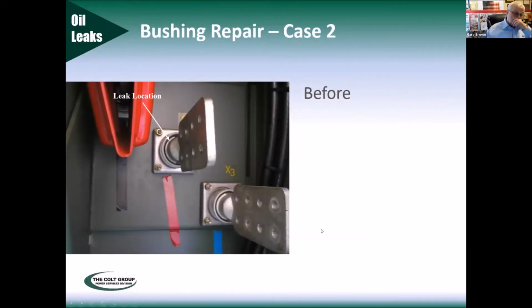And then this particular one, on the smaller transformers, is leaking through that bushing where the porcelain and the aluminum terminal end comes through. In fact, we got one in Kansas City I just quoted yesterday that we're probably going to end up doing, but it's leaking out of here. So we're going to make a nylon clamp with fiberglass bolting that'll close on the OD of the porcelain. It'll come over and close on the OD of this terminal end right here.